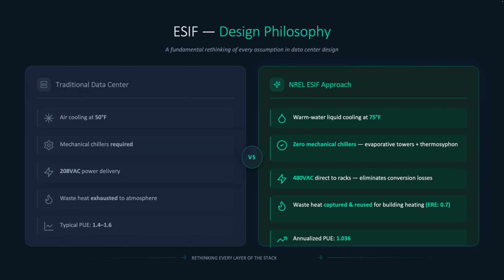We really pushed to bring warmer temperature water to the computing systems. Traditional design always said you've got to have 50-degree F water, and we looked at it going, people are happy up to about 75, we should push to there. And the chip is perfectly happy at 140. As a mechanical engineer, I'm like, there's a lot of room there. So we drove to what we were calling warm water liquid cooling on the ESIF facility.